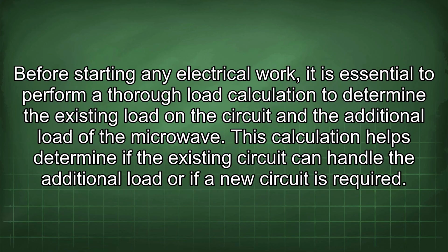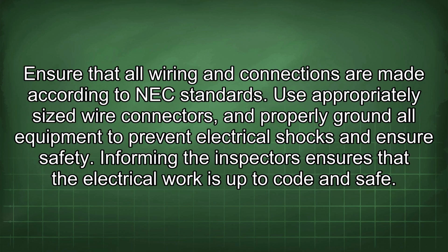Before starting any electrical work, it is essential to perform a thorough load calculation to determine the existing load in the circuit and the additional load of the microwave. This calculation helps determine if the existing circuit can handle the additional load or if a new circuit is required. Ensure that all wiring and connections are made according to NEC standards. Use appropriately sized wire connectors and properly ground all equipment to prevent electrical shocks and ensure safety.